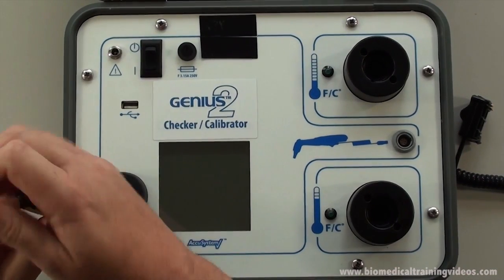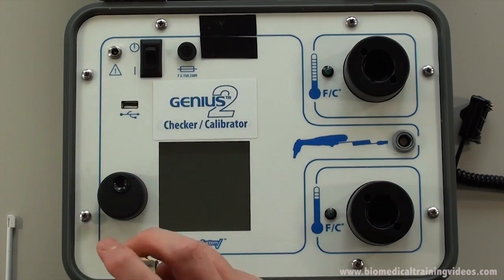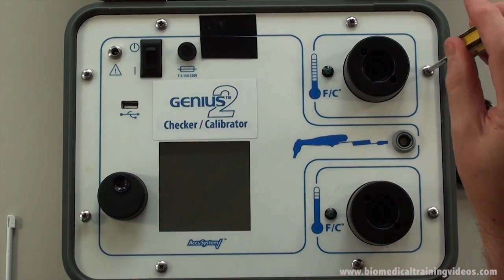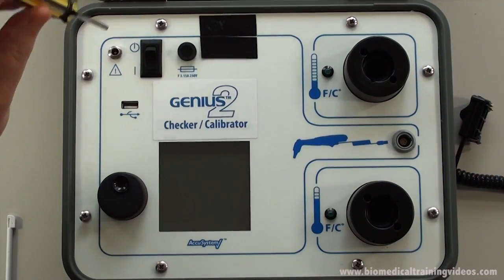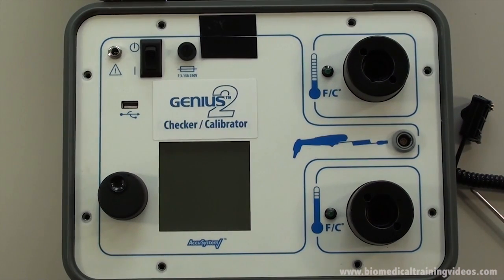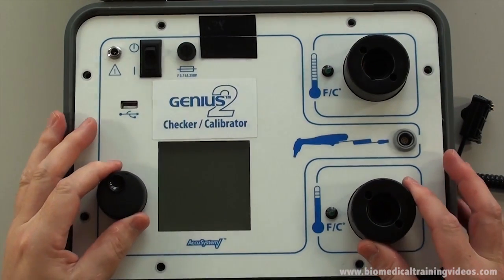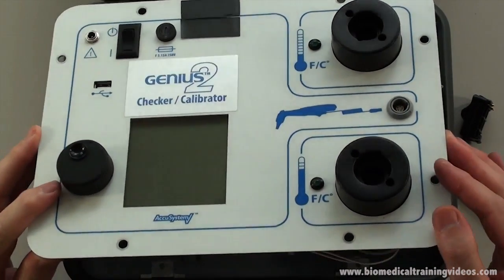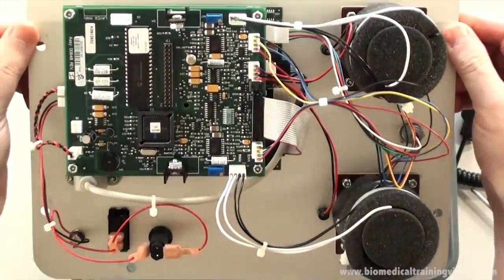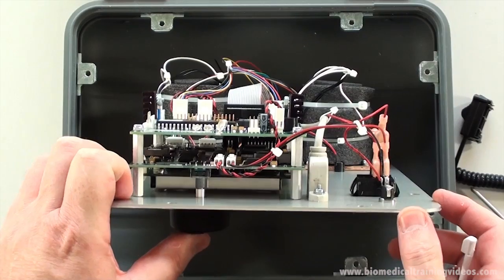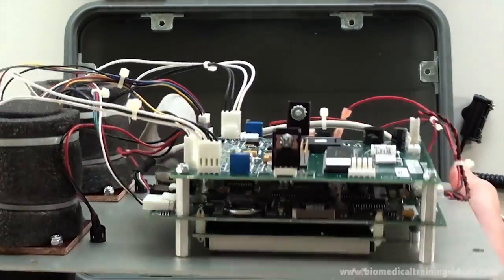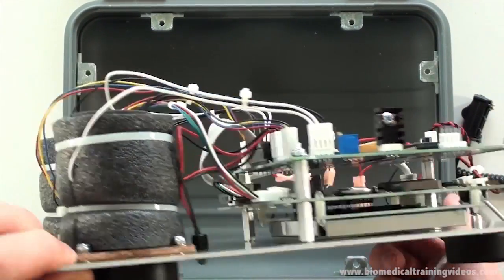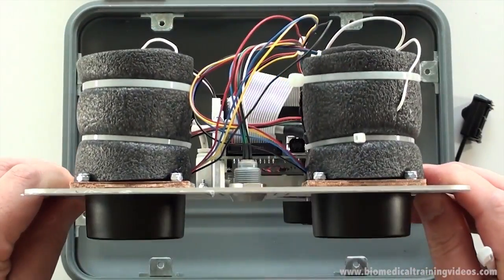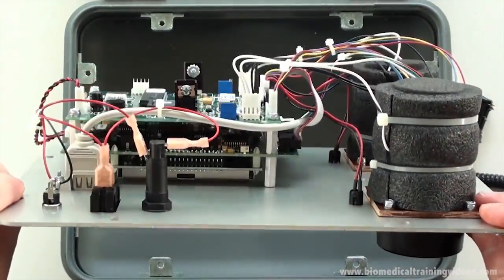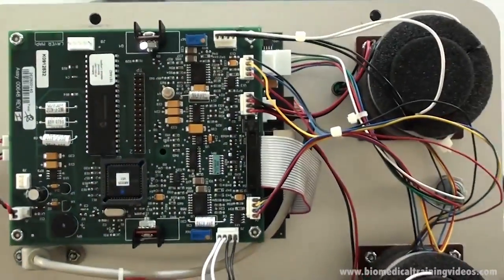Just taking apart the calibrator itself to show you what's inside. Few screws. Again, I've just sped this up a bit. There we go. As you can see, very nicely put together. The 2 targets there, some thermal shielding around them to maintain a constant temperature. Note the 2 trim pots there on the calibrator that are used to calibrate it, so annually you may need to send the unit away for calibration.